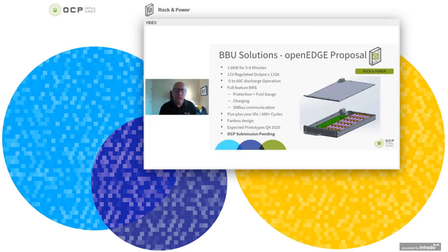It's a 1.6 kilowatt battery pack, which is putting out 12 volts of regulated current at 133 amps. It's a fairly wide temperature range of operation from -5 to 60 C discharge. We do have in the future plans to have something that's going to be able to support an even wider temperature range. This is a full feature battery backup unit with a BMS that incorporates the protection as Alias had gone through, fuel gauging, onboard charging.